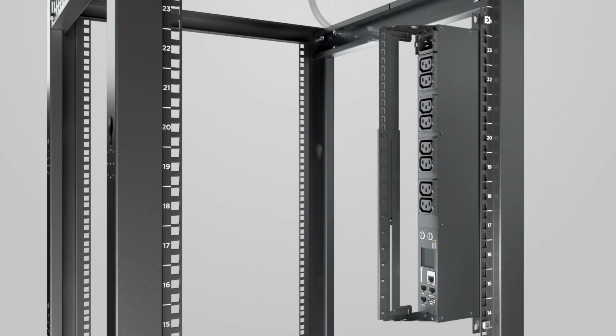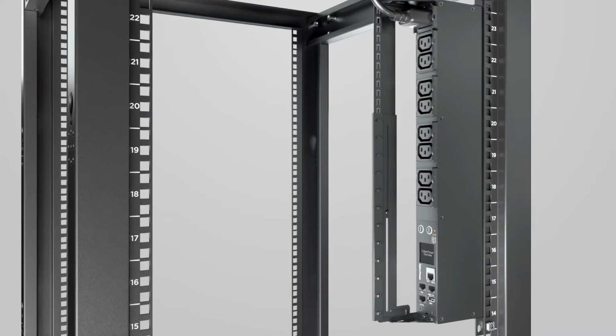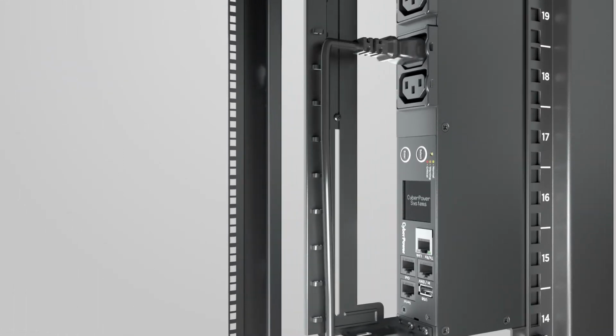To complete the installation, connect the power cord to the PDU and to a UPS system or the utility grid. For connected equipment, use the cable ties to secure and organize the power cords.